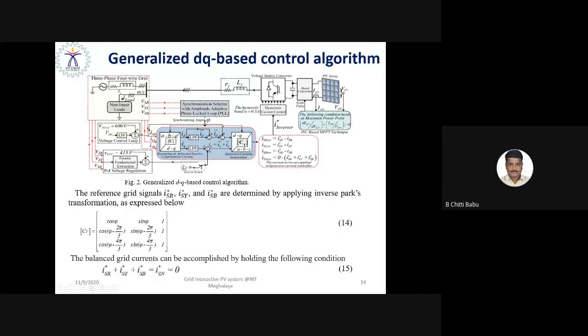The IQ component is basically responsible for the reactive power generation or reactive power injection. During steady state, when the grid is balanced, there is no need for reactive power support, so IQ is assumed to be 0. But this contributes certain reactive power injection when the grid needs the support of reactive power. At that time IQ is not equal to 0. Then the components ID, IQ are transformed again with the inverse transformation to ABC. Then we are able to generate the reference currents ISR, ISY, ISB star, so the three-phase reference current.